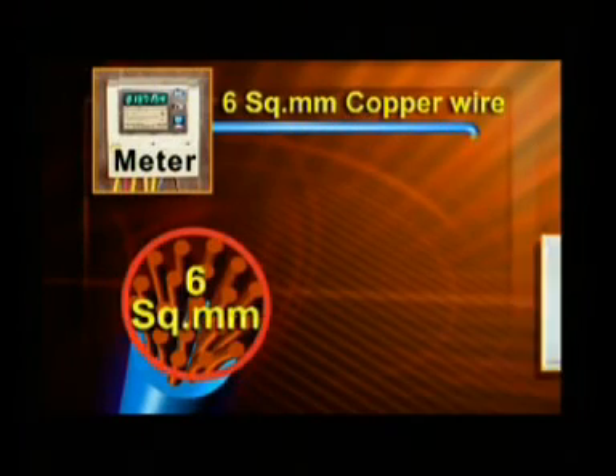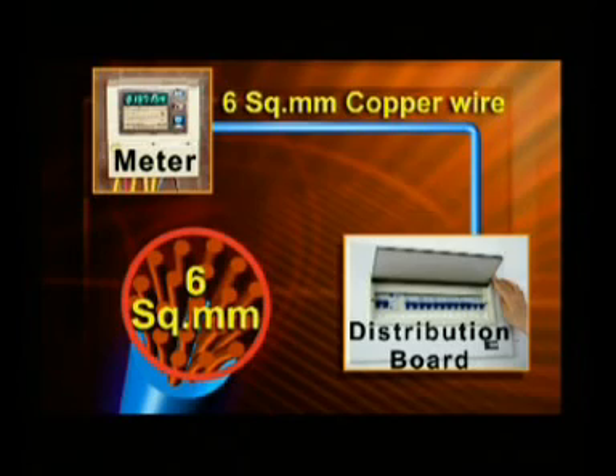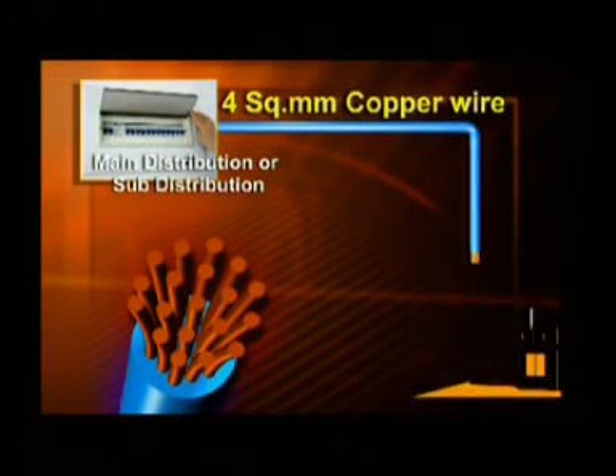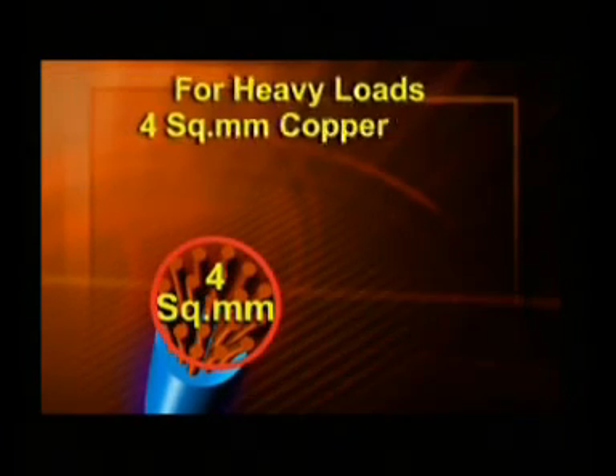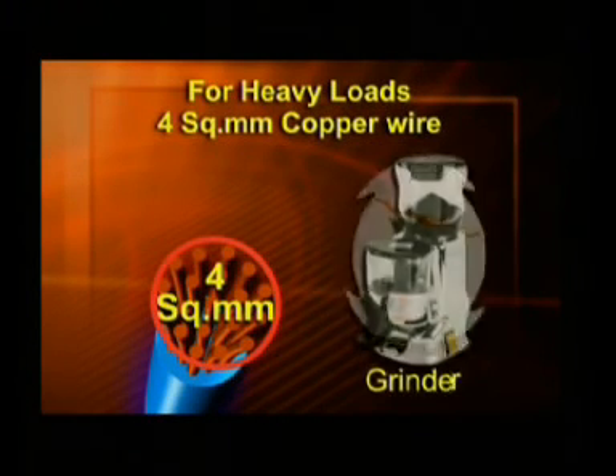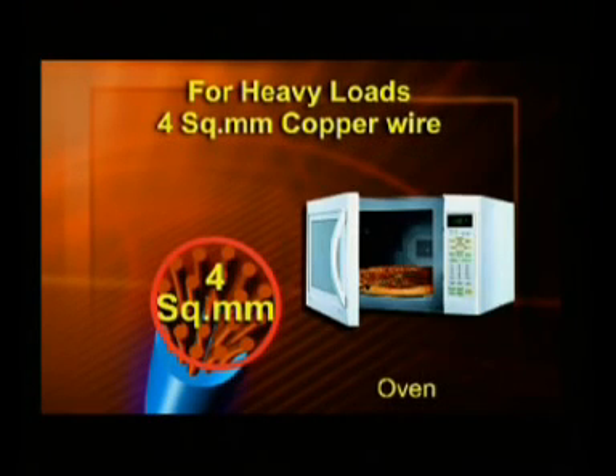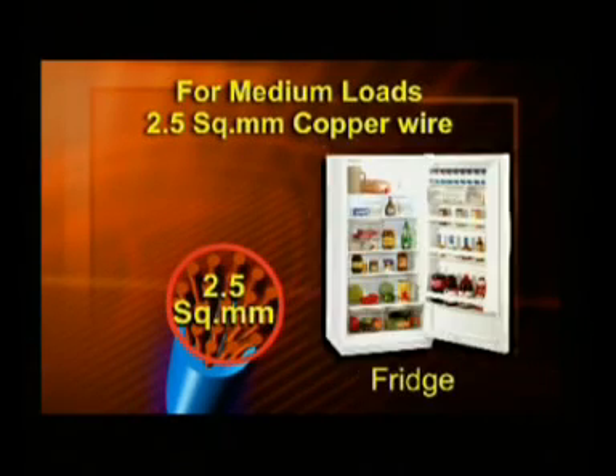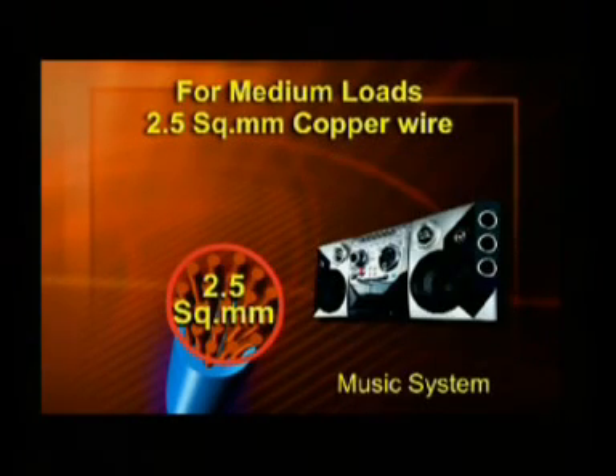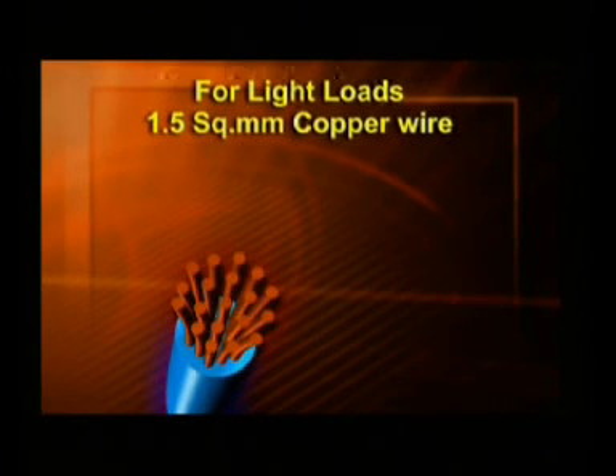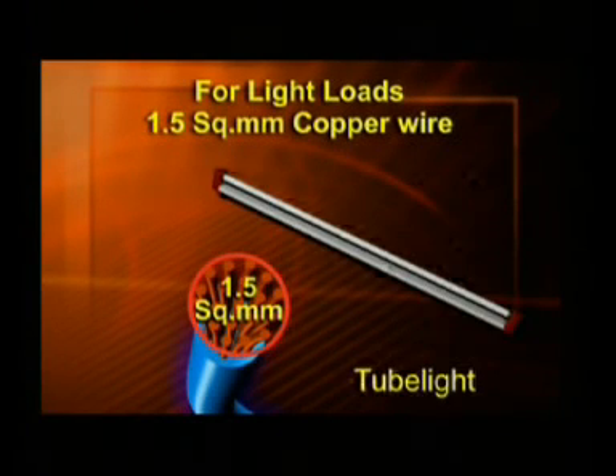It is advisable to use wires of 6 square mm from the meter to the main distribution board. From the main distribution board or the sub-distribution board to different rooms, and for heavy load equipment such as AC, geyser, grinder, washing machine, oven, etc., use 4 square mm wires. For medium load items such as TV, refrigerator, computer, music systems, wire of 2.5 square mm, and for light load items such as bulbs, fans, tubes, use 1.5 square mm wires. Follow the guidelines given in this regard in Part 8 of the National Building Code of India 2005 Building Services.